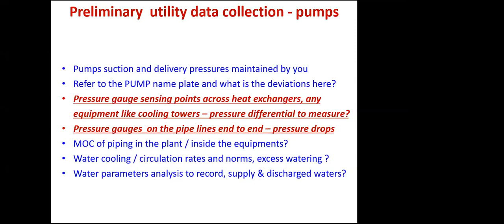You see here the pressure gauge sensing points across the pumps on the suction and discharge, on the heat exchangers on the suction and discharge, and on the cooling towers, where the pressure differentials are to be measured. You see that the provisions are there. When the energy auditor comes in, the readings are easily accessible to us. Whenever we go to any pumping mechanism in an industry, we find the pressure is not measurable at all because the pressure gauge is not working. When we do the energy audit, we may do it for 3 or 4 days. At that time, to fix a pressure gauge on the pressure line, they will say they have to switch off the equipment, they have to switch off the process. It is not going to happen immediately.